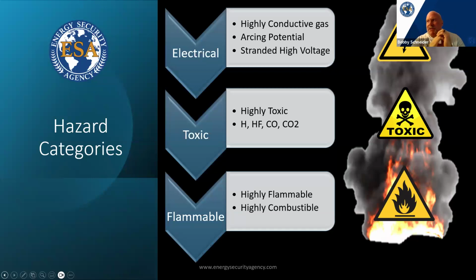Also, most of the HF we're seeing in our own tests, and in other tests we've looked at, isn't constant. It's happening in bursts, 2 to 3, maybe 4 or 5 second bursts. In our testing, we see a spike in HF right before combustion. Then once combustion happens, it burns up the HF and all the other VOCs. So here's another hint: if it's doing something bad and it's burning, it's far better to be burning than to be off-gassing without burning, because you're burning up a majority, if not all, of the bad stuff during combustion.